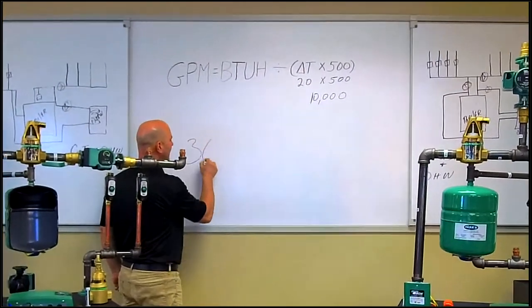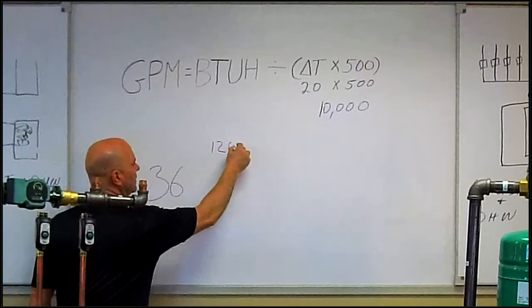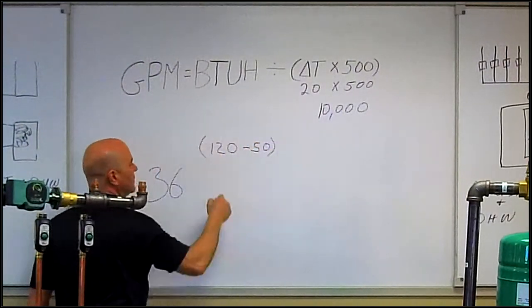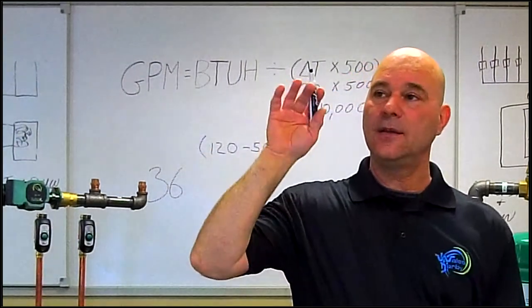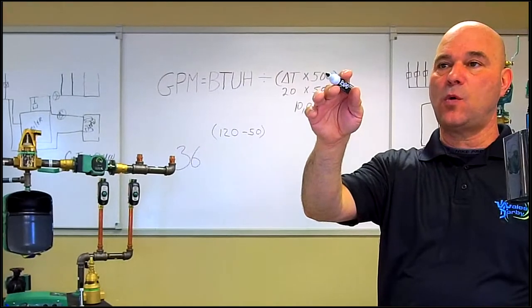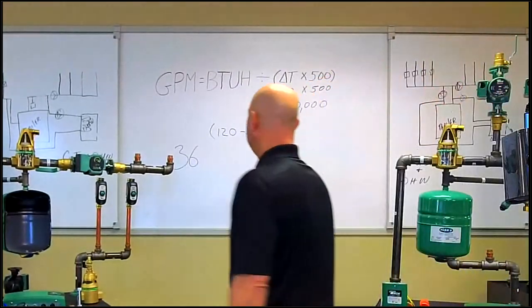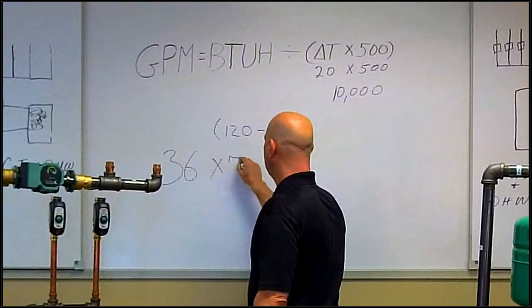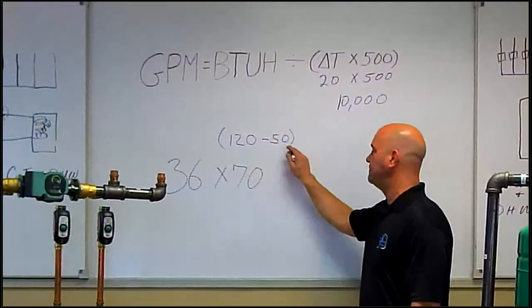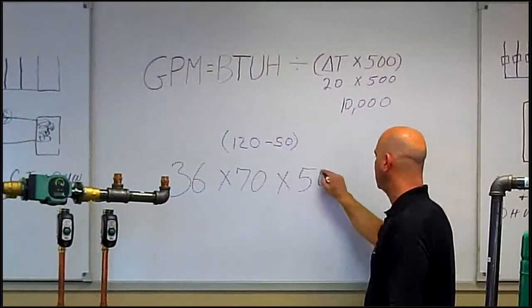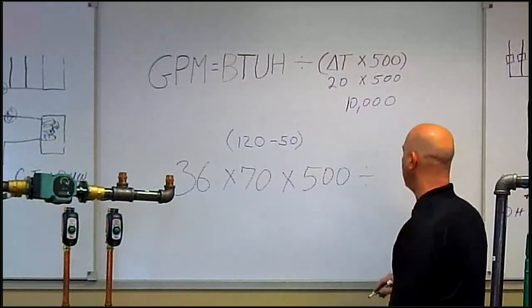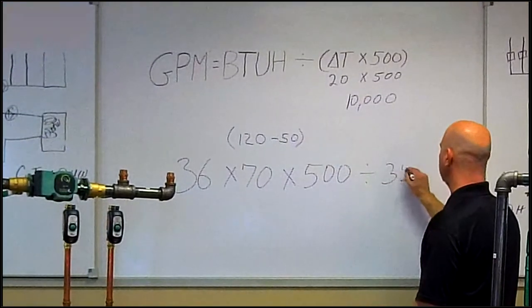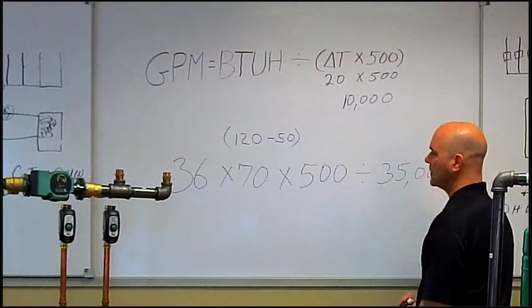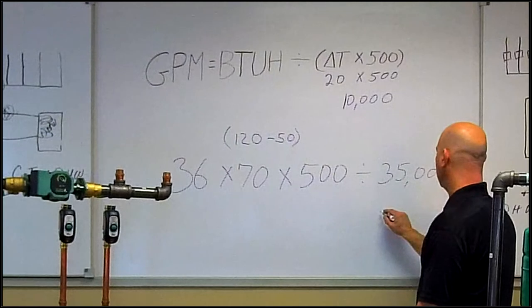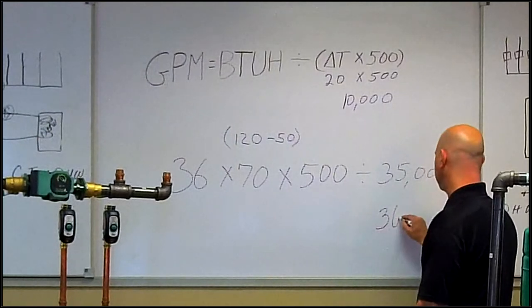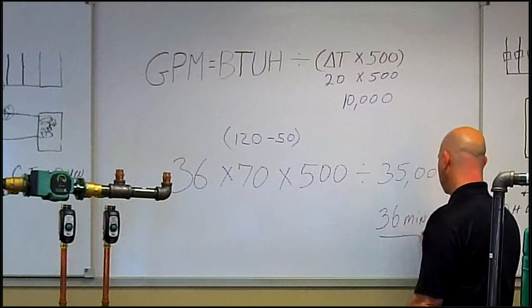We have a 36 gallon tank. We had 120 minus 50. And again, that is delivery temperature of 120, incoming water temperature at 50. That's 70 degree difference here, right? Multiply that by 500. And then I'm going to divide that by, again, I got a Honeywell zone valve. A Honeywell zone valve moves 35,000 BTU. So when I multiply this out, that is going to give me approximately 36 minutes. Yep. 36 minutes to heat up that indirect.